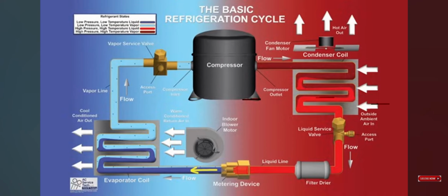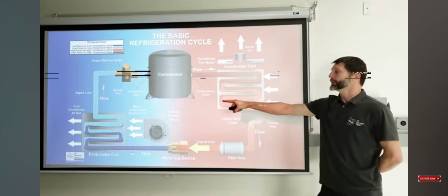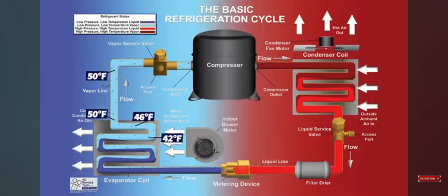And that is because anytime that the refrigerant is saturated where liquid and vapor exist, it's always the same temperature as it travels through the coil until, in this case, it becomes a vapor state, in the fully vapor state. Once it becomes vapor, it can then increase in temperature as the hot air is blowing across the coil. The refrigerant's going to absorb heat energy, a low pressure, low temperature vapor refrigerant exiting the indoor evaporator coil.